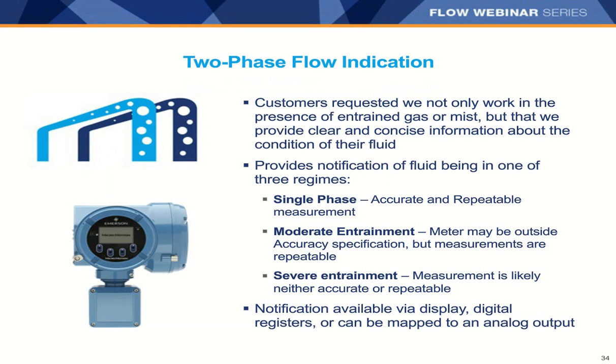The 5700 provides two-phase flow indication — think of it as a green, yellow, and red light for your process. Green means single-phase, accurate and repeatable measurement. Yellow means moderately entrained gas and the meter may be outside accuracy specification. Red means severe entrainment where the meter is likely neither accurate nor repeatable due to severe two-phase flow.